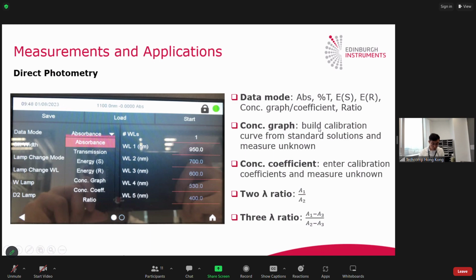For the ratio, there are 2 or 3 wavelengths you can select. For the 2 wavelength ratio, the first absorbance will be divided by the second absorbance to give you the ratio of the 2 wavelengths. And for the 3 wavelength ratio, the third wavelength will be used for the calibration, and then you can see the calculation of the wavelength ratio here.